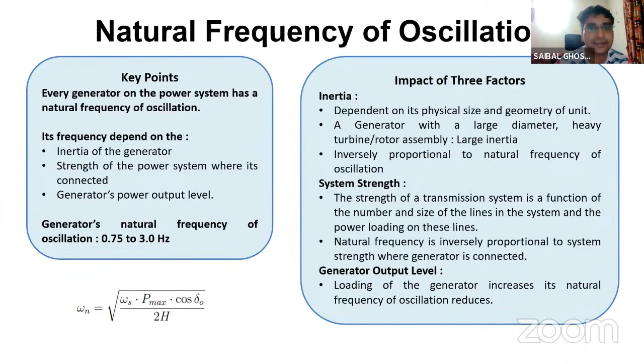The oscillation frequency depends on these three factors. As we have already mentioned, it is a nonlinear equation, so the point at which the system is operating is very important. This is denoted by the generator output level, and system strength is nothing but the equivalent impedance seen by a generator. Think about only one generator oscillating against the system. If that generator is connected to the grid through only one single, very long line, its impedance value will be very high. So the effective system strength seen by the controller of that generator will be very low, and that's why there is a chance of oscillations when there are weak interconnections. Inertia is already explained.